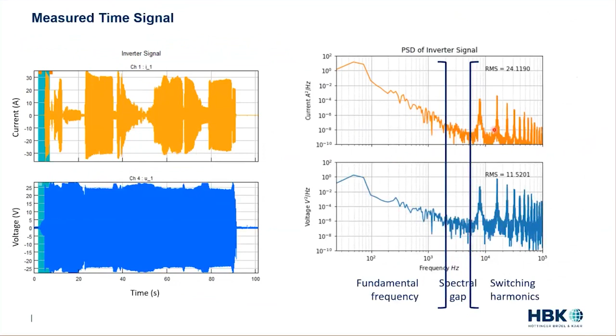So, if we isolate the fundamental frequency by putting in a low-pass filter, and the low-pass filter I've actually put in just about here, at around 5,000 to 6,000 hertz. I've not put it in low, and the reason for that is Mitch was pointing out we need the harmonics of the fundamental, so you just need it at a point where you filter out the switching harmonics, but you've still got those high-order fundamental harmonics. And what we end up with then is this nice plot here.